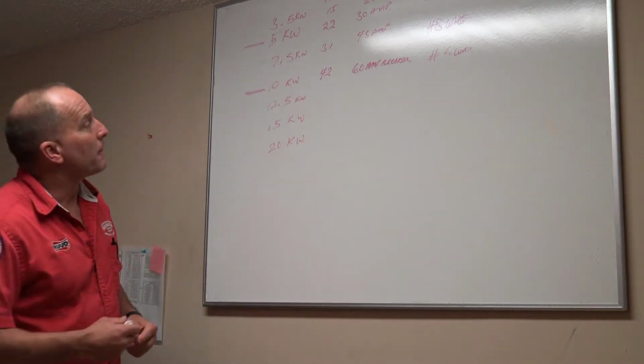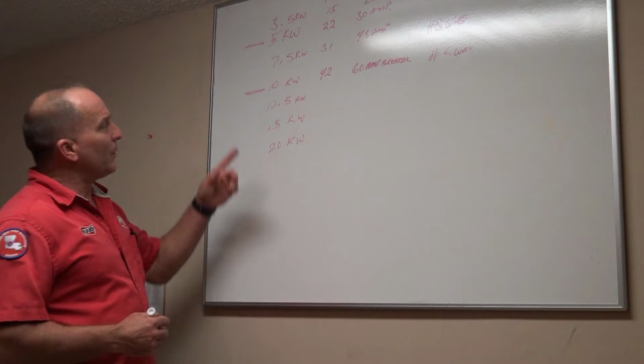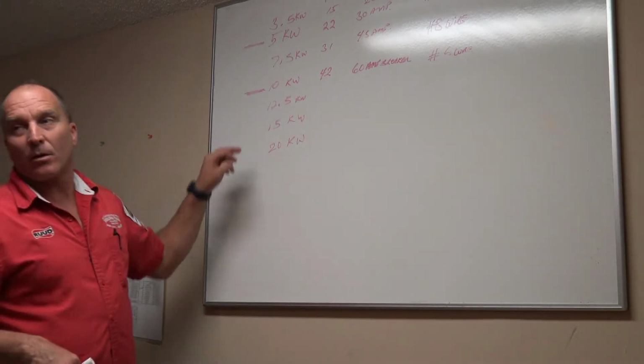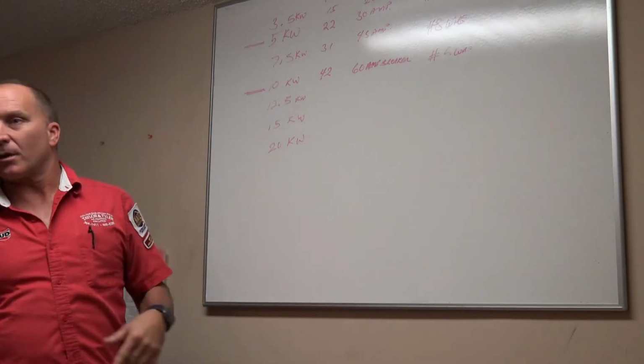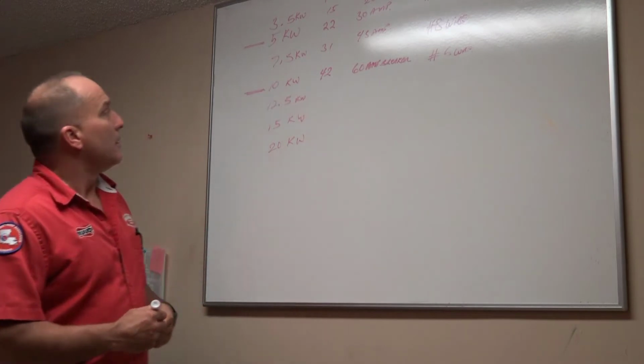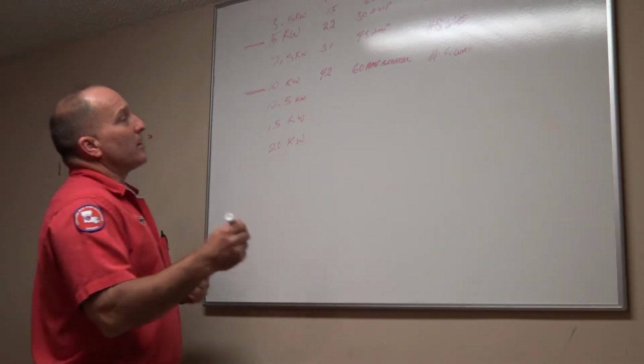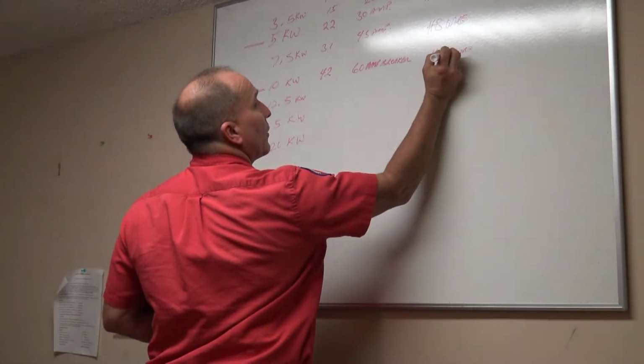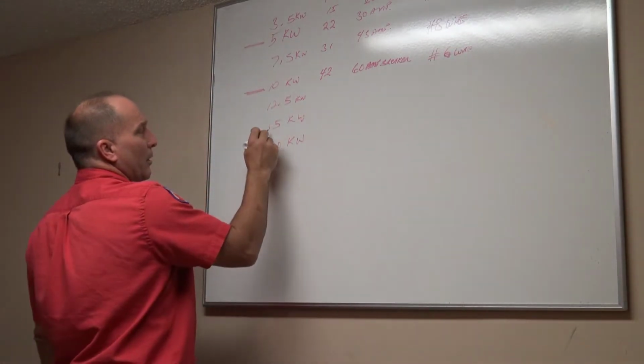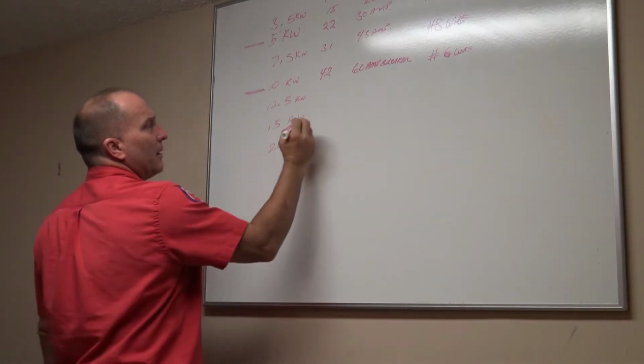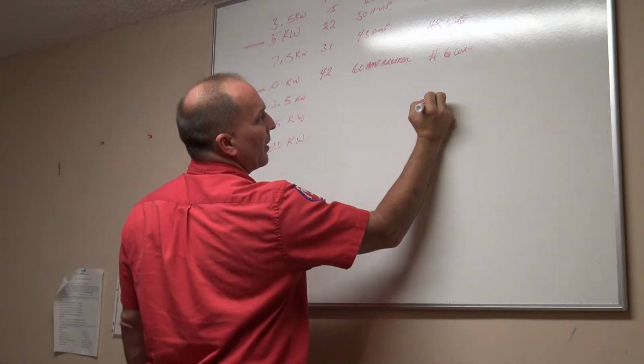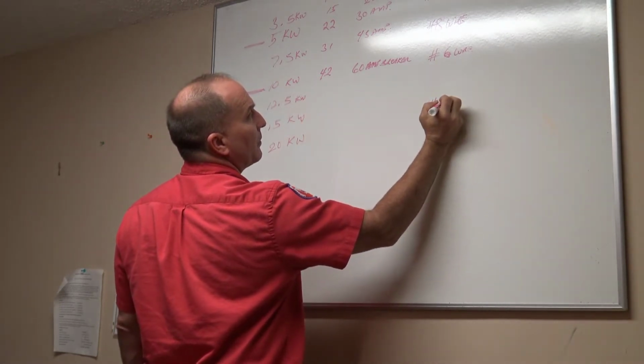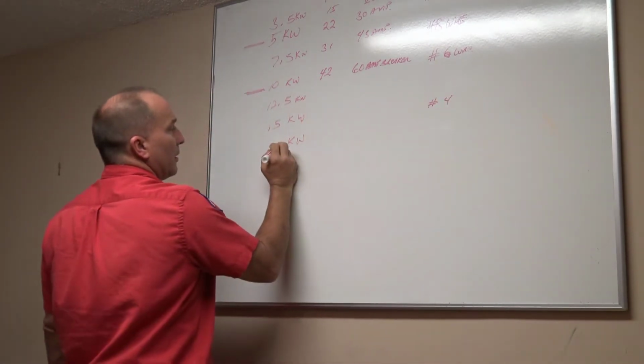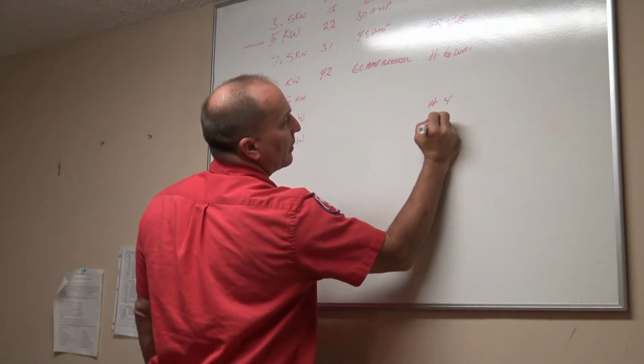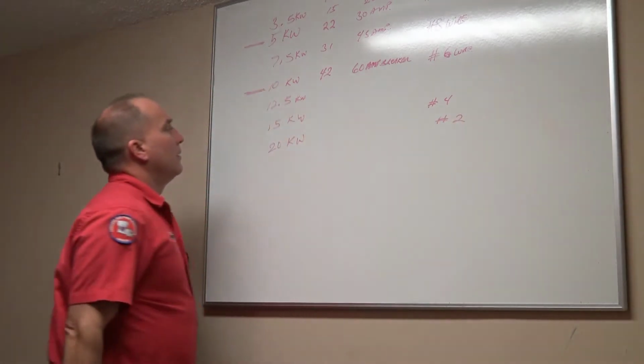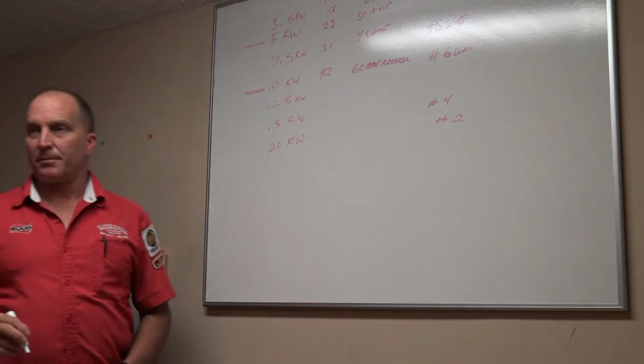All right. We threw an extra one in here that's not in the paperwork, a 12.5. We're going to skip it. We're going to go back to it for a second, okay? So here's a number 6 wire. Now we're going to go to 15 kW heat, and we're going to come all the way over here. And what's my next wire size up? Number 4 wire. Then we're going to go to number 2 wire for a 20 kW heat system.